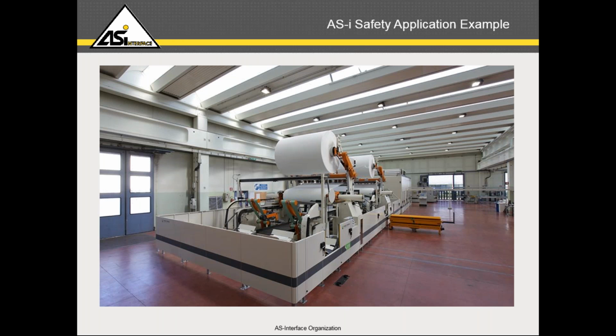So because it's a locking switch, you need a request to enter, as well as a control to lock once the operator has exited the machine. Also, the machine has a reset button to reset the safety function. And once the reset of the safety function is done, you need a lock command. So since this machine has a reset command, a lock command, and an unlock command for each interlock, additionally, we have also emergency stop for each interlocking door entry area.